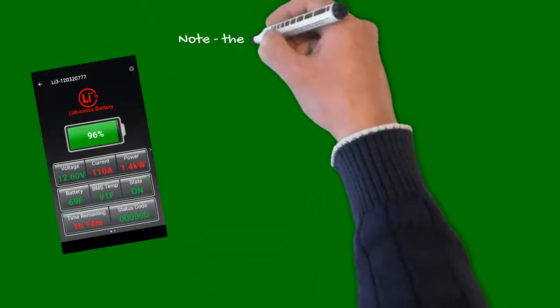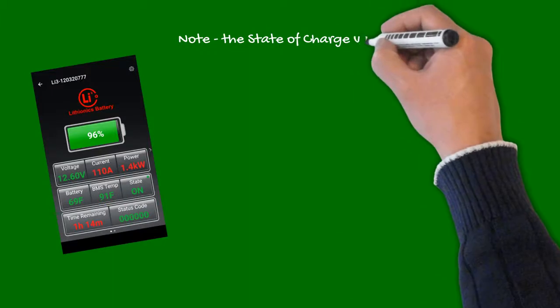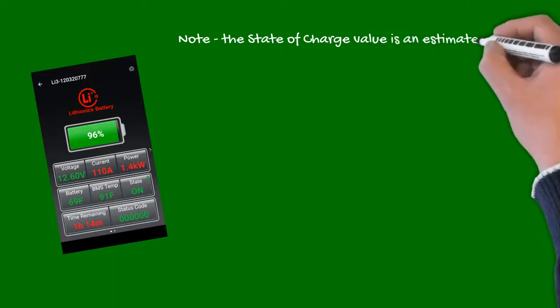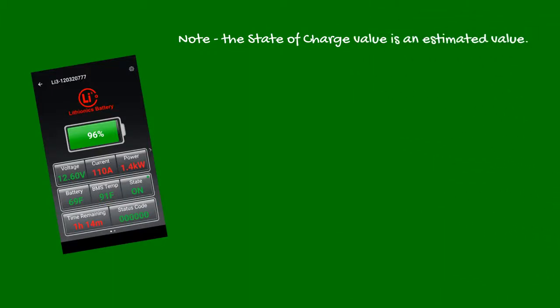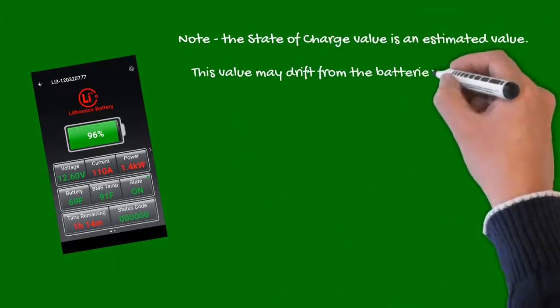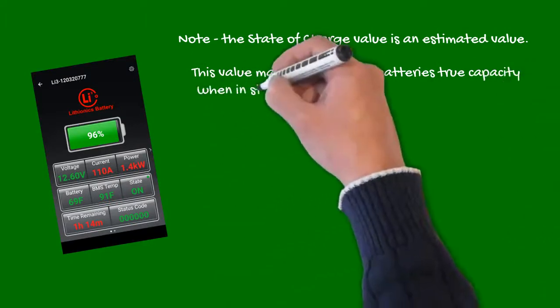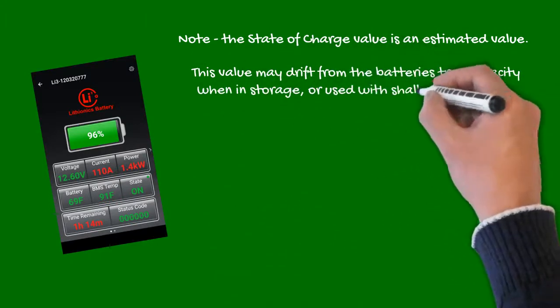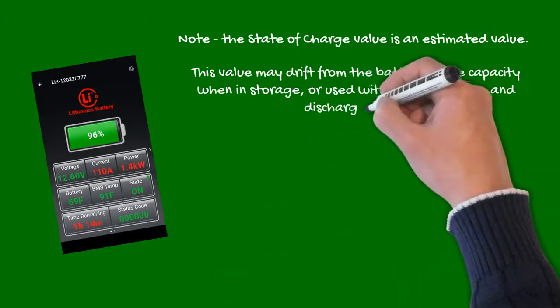Please note, the state of charge value is an estimated value. Over time this value may drift from the battery's true capacity. This is especially true when the battery has been in storage, or used with shallow charge and discharge cycles.